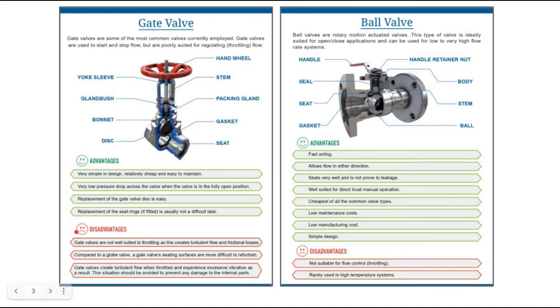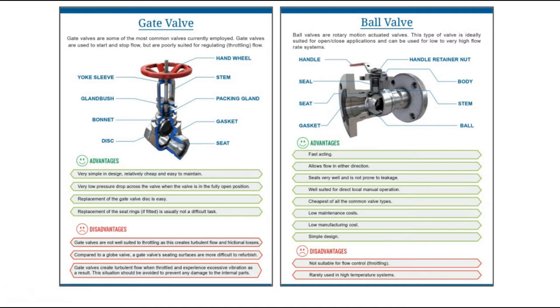Disadvantages of gate valves: they are not well suited for throttling as it creates turbulent flow and frictional losses. Compared to a globe valve, a gate valve's seating surfaces are more difficult to refurbish. Gate valves create turbulent flow when throttled and experience excessive vibration as a result. This situation should be avoided to prevent damage to the internal parts. The replacement of seat rings, if fitted, is usually not a difficult task.